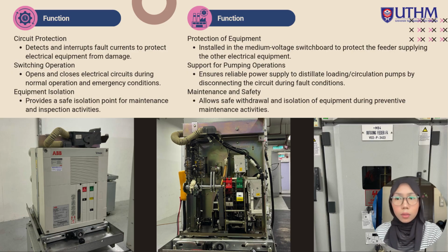The vacuum interrupter extinguishes the electrical arc quickly, reducing contact wear and maintenance requirement. At ATB, the VCB protects feeders supplying variable speed drive and medium voltage motor used in pumping operation. This ensures that any electrical fault is isolated locally without affecting the entire distribution network. The VCB plays a vital role in maintaining electrical system reliability and personal safety.